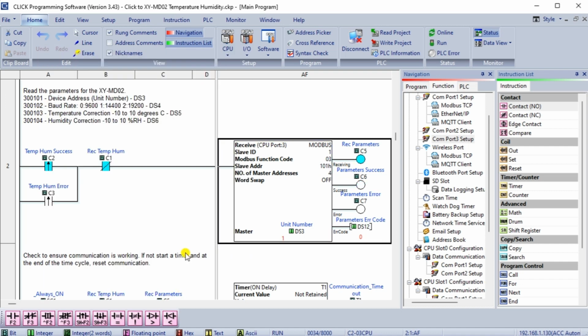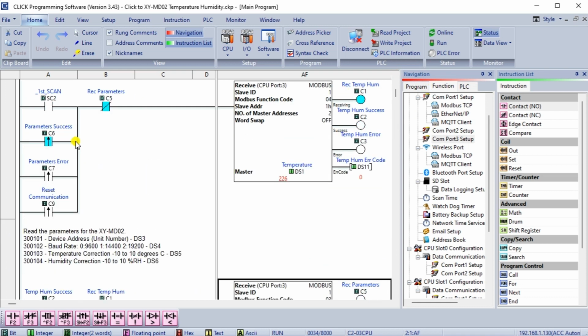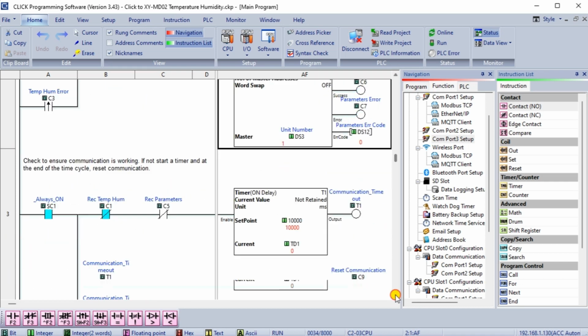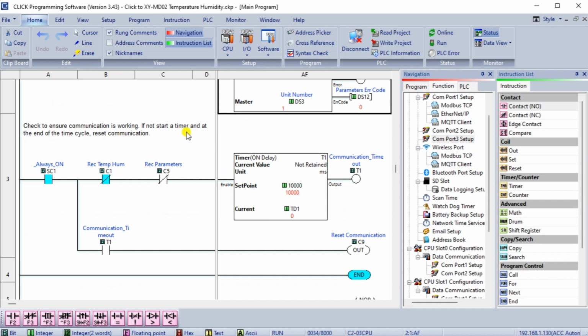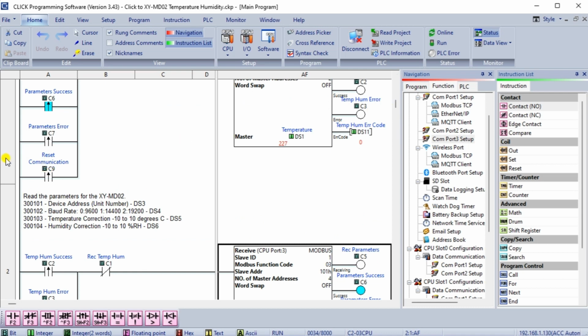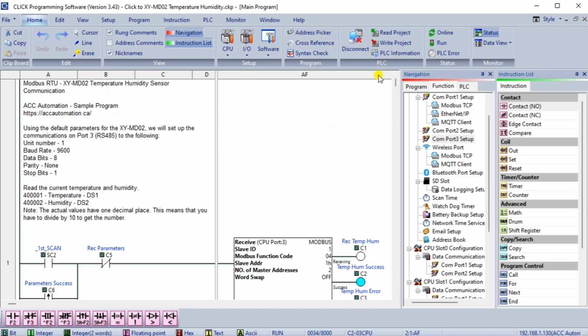Here is rung 2 of the click ladder logic code. The parameters will read when the temperature and humidity read is success or failure and the receive bit is not on. Notice that the receive, success, and error bits for the parameter reading are used in rung 1 for the first read. The third ladder logic rung will set the timer if the receive bits for the Modbus reads are not activated within 10 seconds. Communications will reset when the timer times out. This is the end of our Click PLC ladder logic program. Download this to the controller and ensure that the PLC is running.